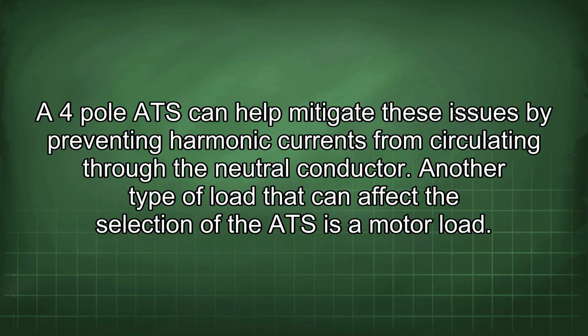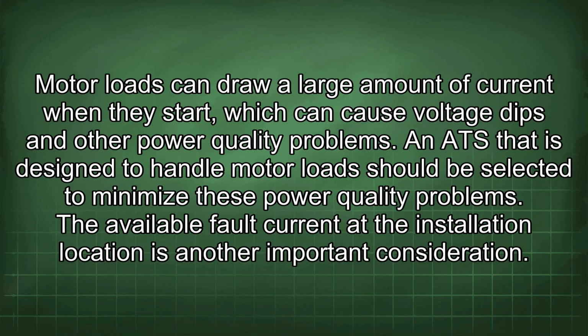A 4-pole ATS can help mitigate these issues by preventing harmonic currents from circulating through the neutral conductor. Another type of load that can affect the selection of the ATS is a motor load. Motor loads can draw a large amount of current when they start, which can cause voltage dips and other power quality problems. An ATS that is designed to handle motor load should be selected to minimize these power quality problems.